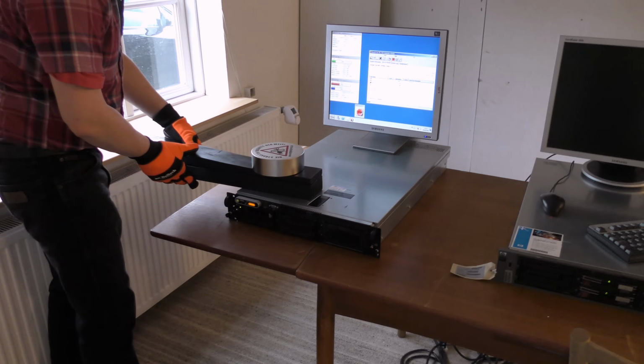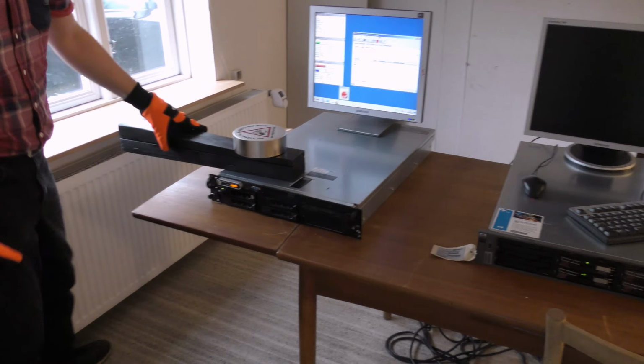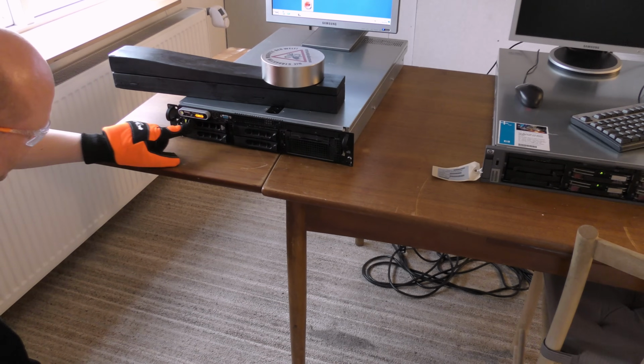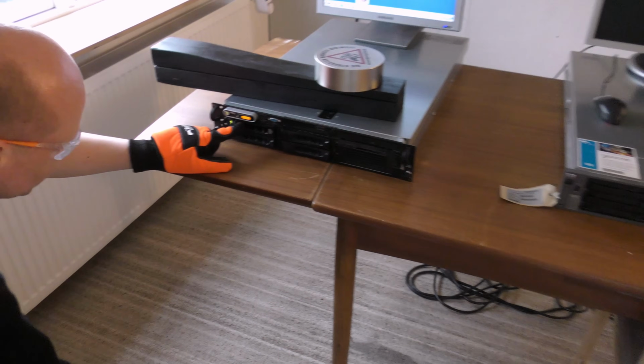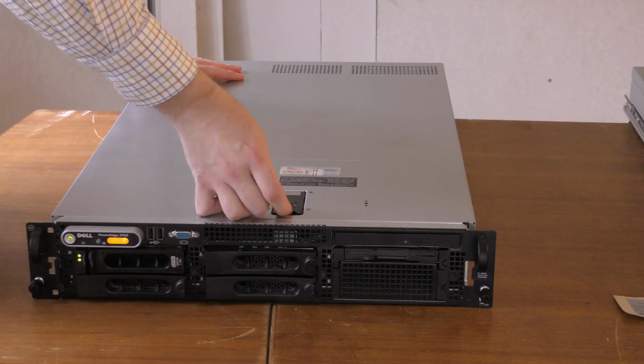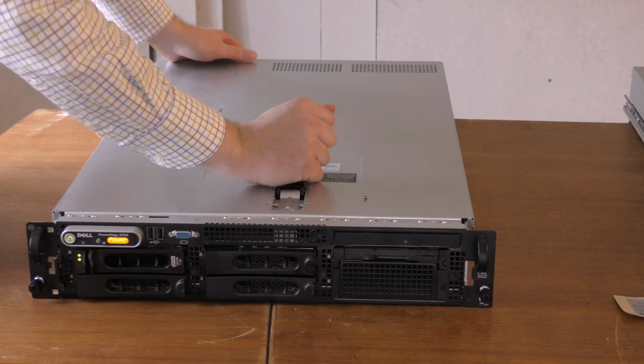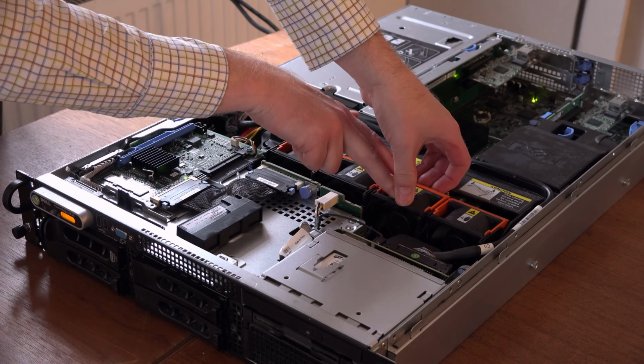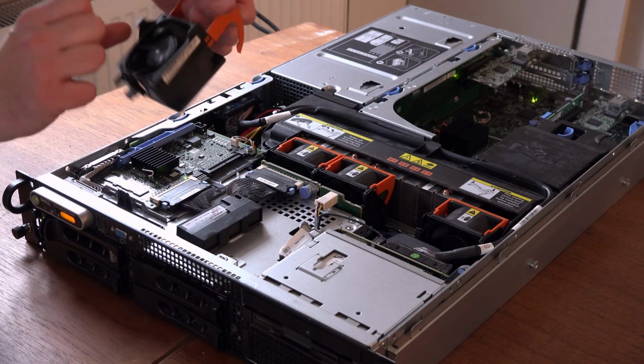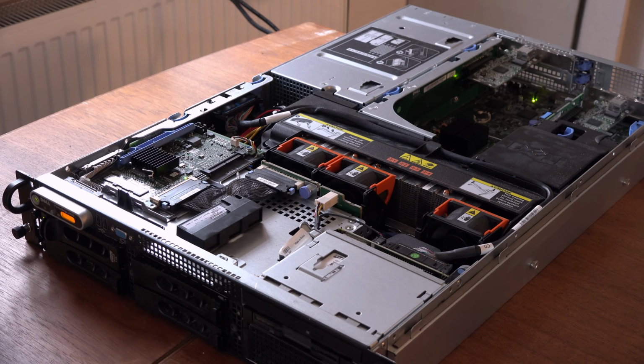Yeah, we have something burning here. The server sounded really angry and smelled furiously hot. It was giving us errors about fan redundancy and fan RPM. When we opened the server, we found that 3 of the 4 fans had stopped working. Not good during a burn-in test.